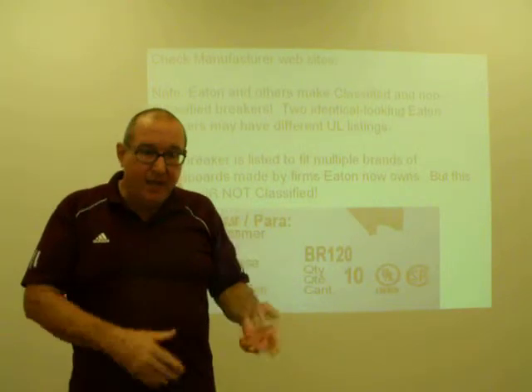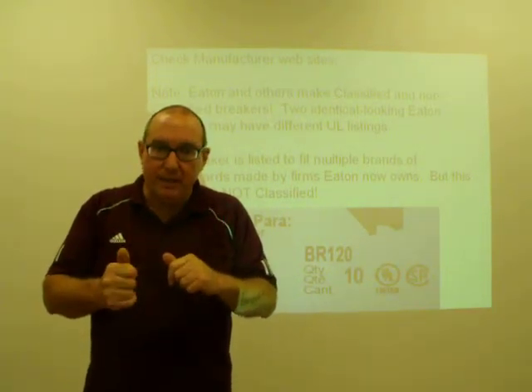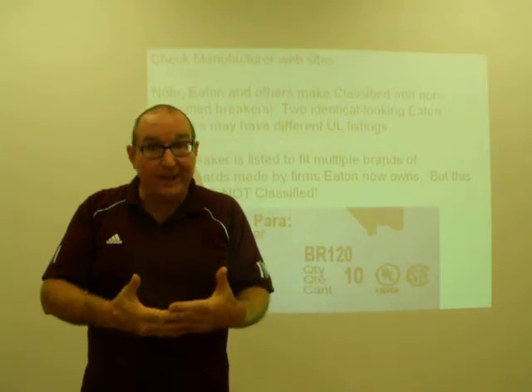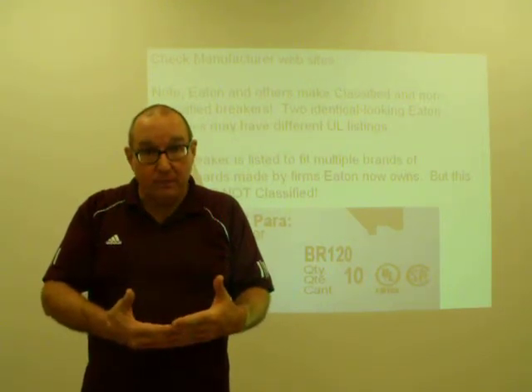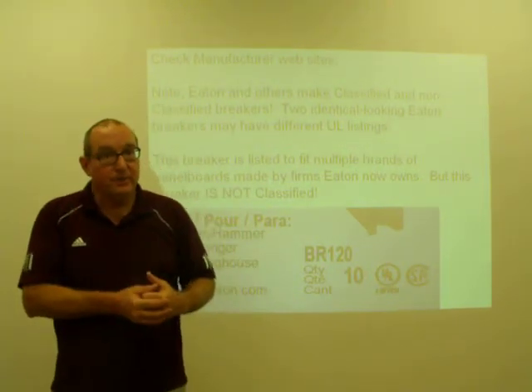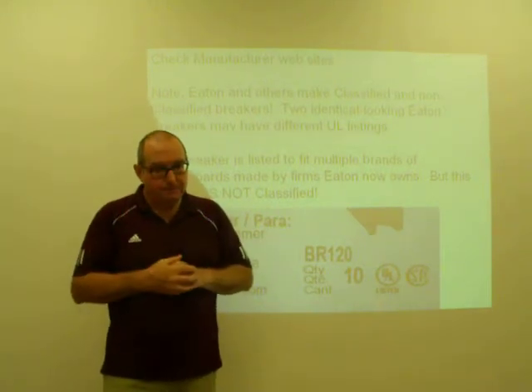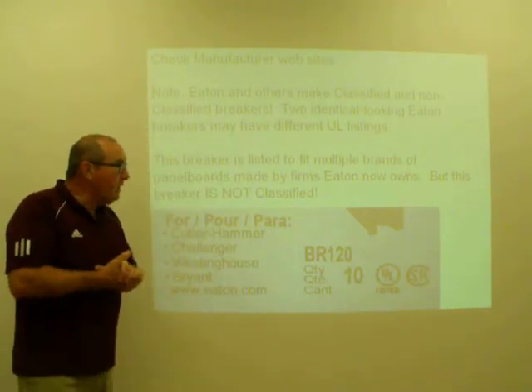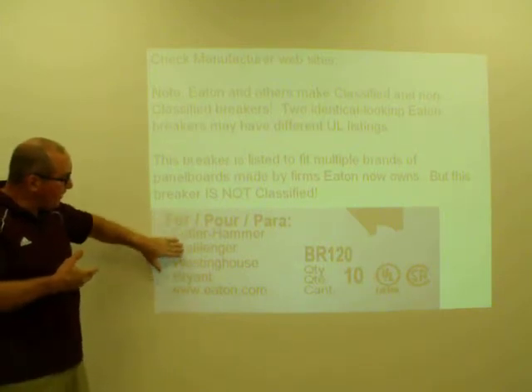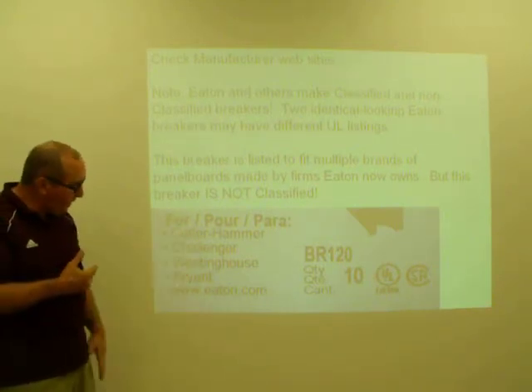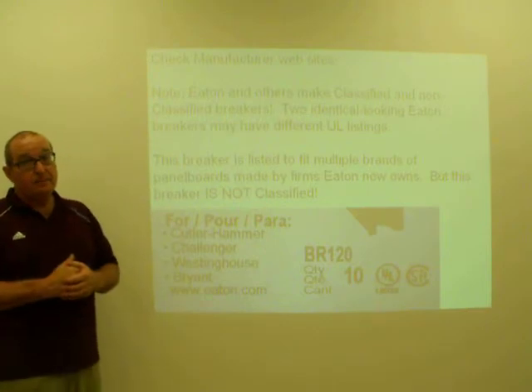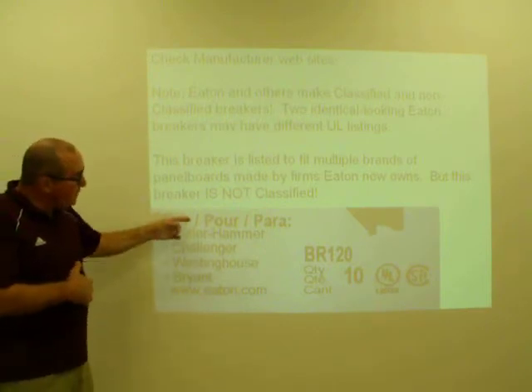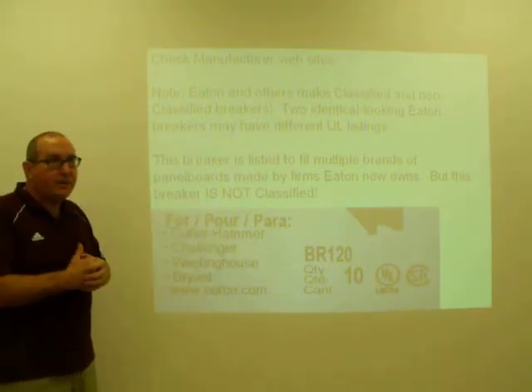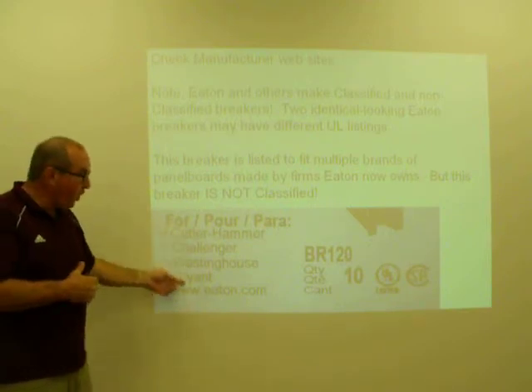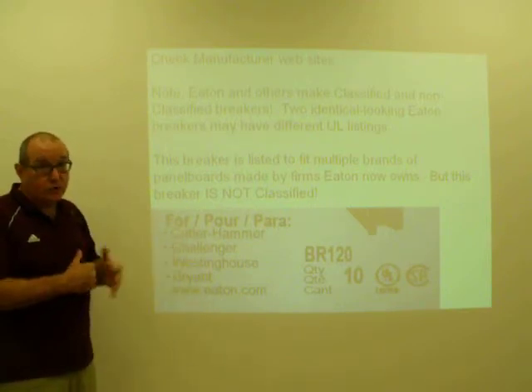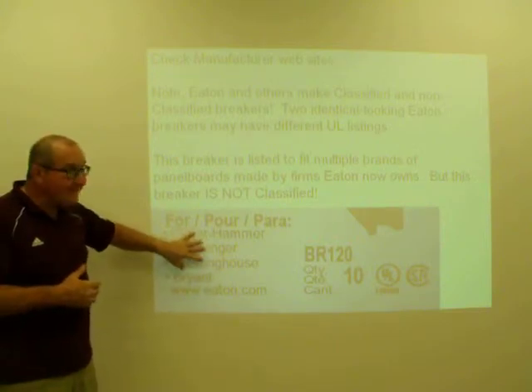And again, as I mentioned, you may have two Eaton breakers side by side. One is classified, one isn't, and yet they physically look identical. I don't know how they tell them apart. I don't know what's different about those breakers that makes one classified and one's not. To be aware of this, Cutler-Hammer, Challenger, Westinghouse, and Bryant over time have all ended up being owned by Eaton. Then this specific non-classified Eaton breaker is listed for use in all the panels that Eaton now owns. That does not mean that this is a classified breaker.